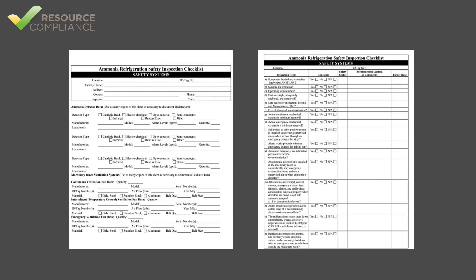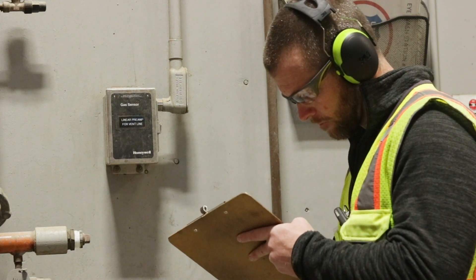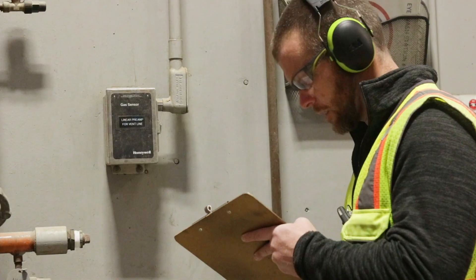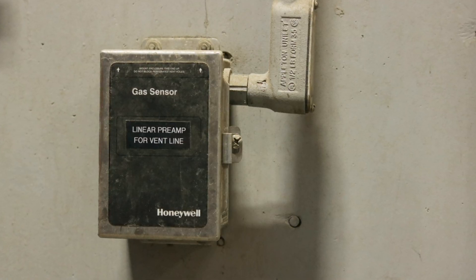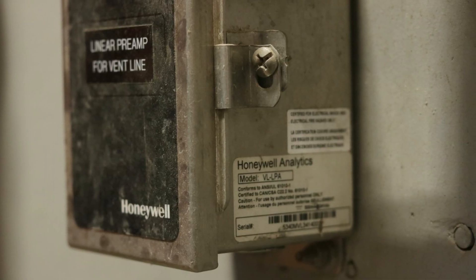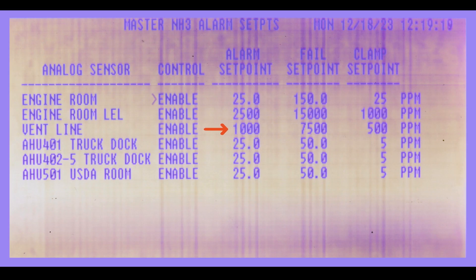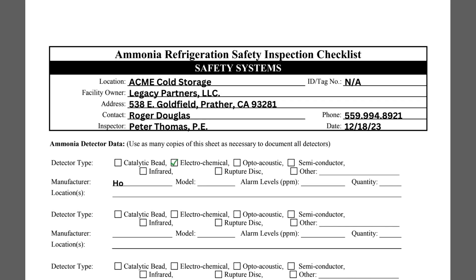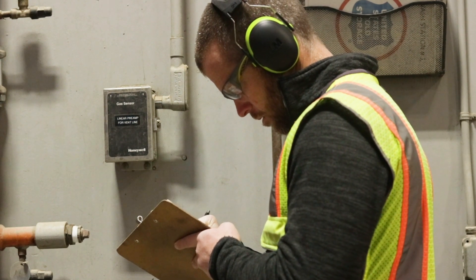After completing the contact information section, the form has a section for ammonia detector data. The inspector should use this section to fill in the relevant ammonia detector information. This detector is a Honeywell Analytics Model VL-LPA electrochemical vent line sensor that is interlocked with the computer control system to alarm at 1,000 ppm and initiate a shutdown at 7,500 ppm. The same information should be filled out for each sensor that is part of the ammonia detection system.